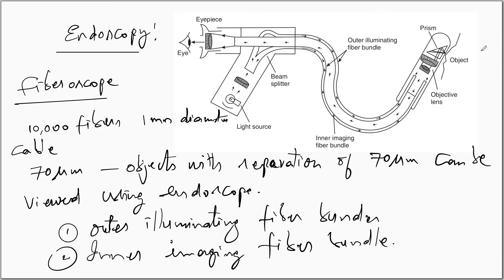After light reflects from the object, it is received by the inner imaging bundle. To make the light enter the inner imaging fiber bundle, there is a telescopic arrangement — the eyepiece and the objective lens together make the telescopic arrangement. A prism is used to make the reflected beam enter the objective lens. Once the reflected light enters the objective lens, it falls on the inner imaging fiber bundle, reaches the eyepiece, and from there one can view the image of the inner surface of the human body. That is how an endoscope works.